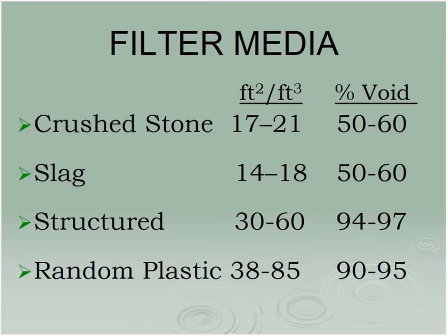The structured packing, that hay bale type of stuff, again, 30 to 60 square feet per cubic foot, again, great void space in there. So if I need to upgrade my plant, all these plants that were built back in the 60s or 70s, those towns are no longer the same size. They've grown considerably. So if they need to upgrade the plant, they can just take out the rock, put in this random plastic, and they're at least doubling their capacity to treat just by doing that. Relatively low capital investment.